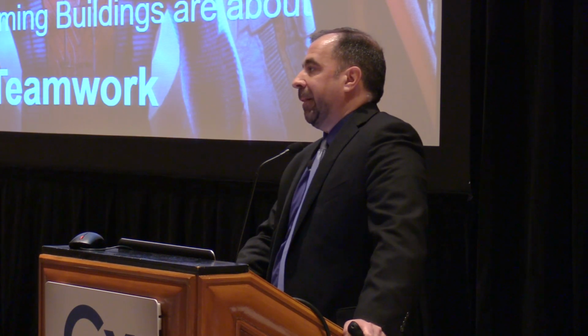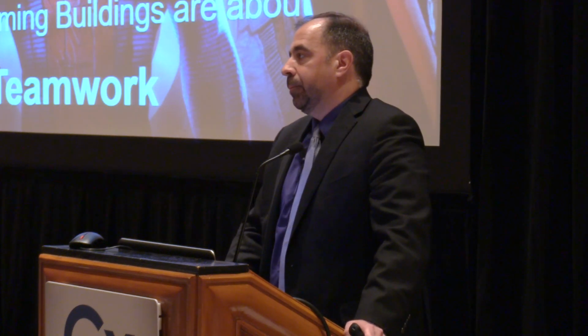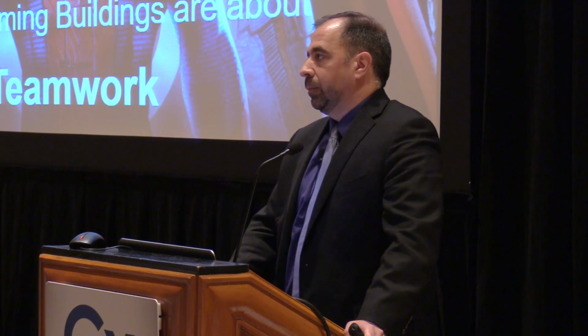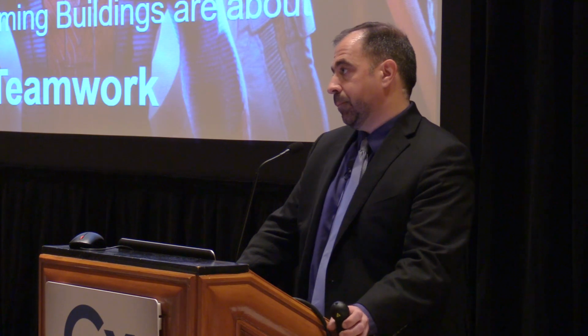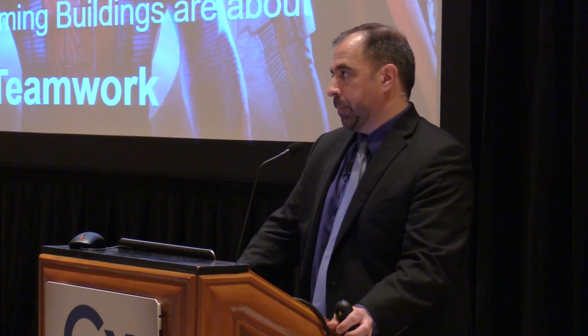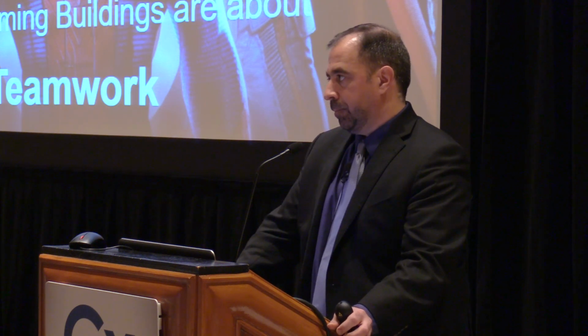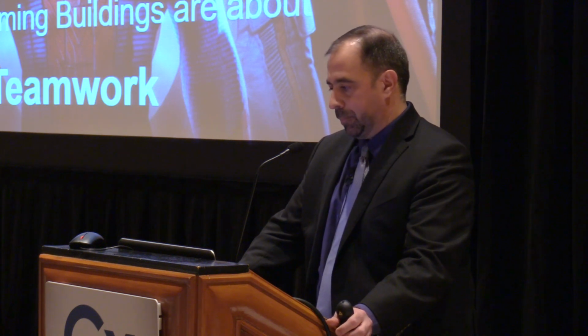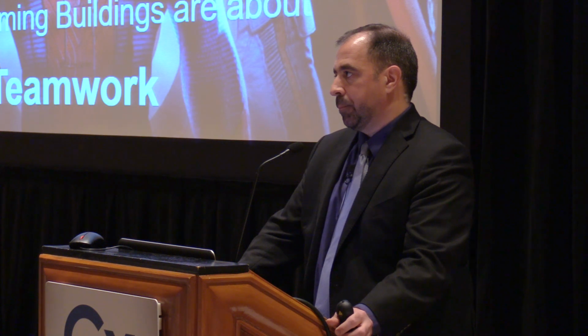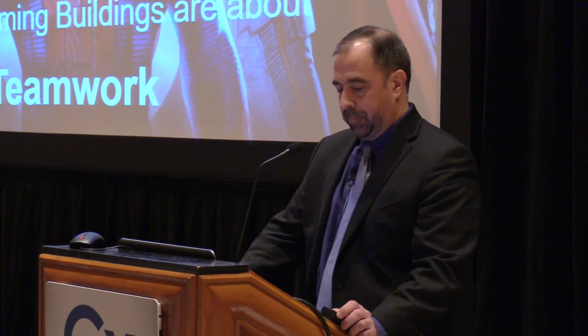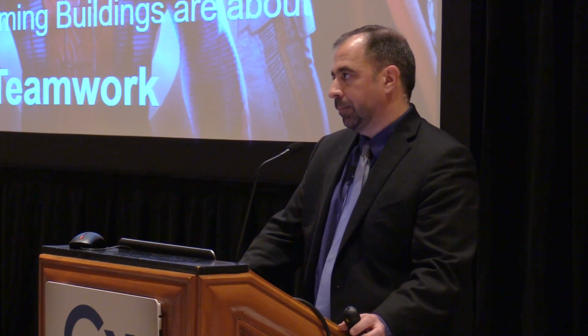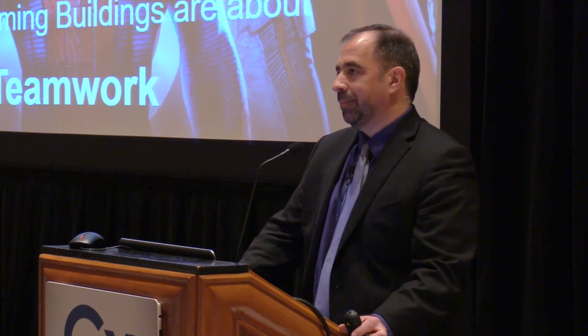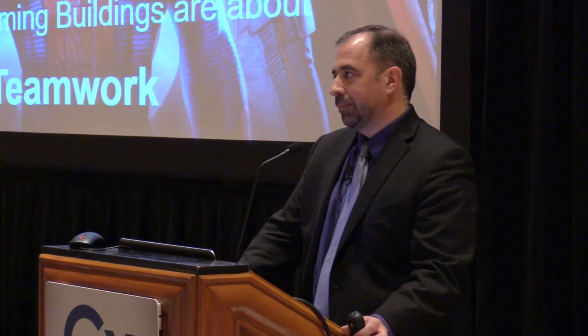This isn't hospital-specific, just a generator question. Do you have issues getting verified success criteria for transient testing? What I see happening is, at the factory, you establish a baseline success criteria based on a 0.8 power factor. But most owners buy a system that's only load bank tested, which is more difficult for a generator to handle when it's tuned to the 0.8 power factor. So you're scratching your head doing the math. This is something I run into quite a bit because there's really no solution - it requires them to do the testing at the factory as well, or bring in a system reactive load to the site, which adds a lot more money, and the owner doesn't want to do that much load bank testing.